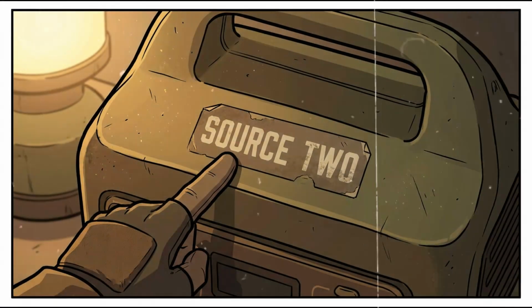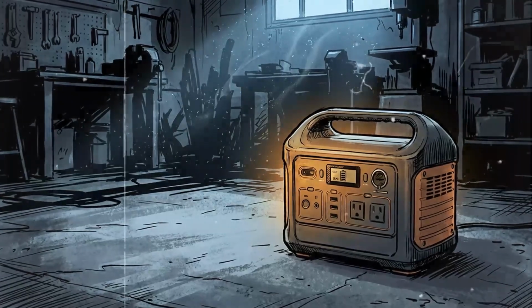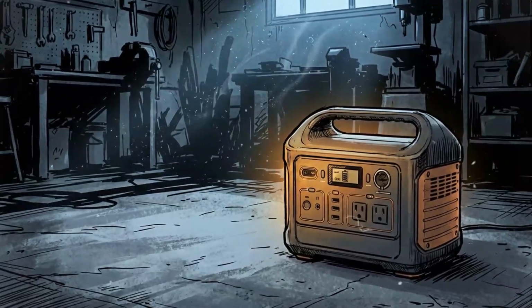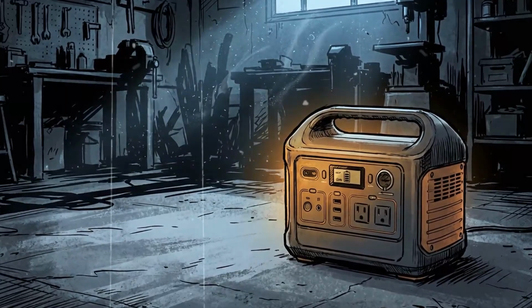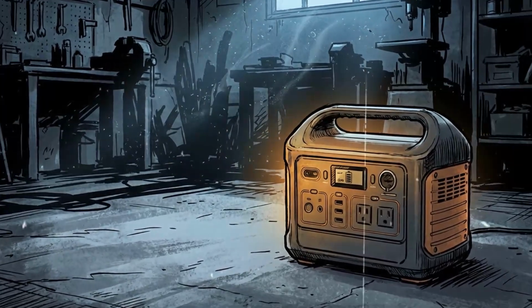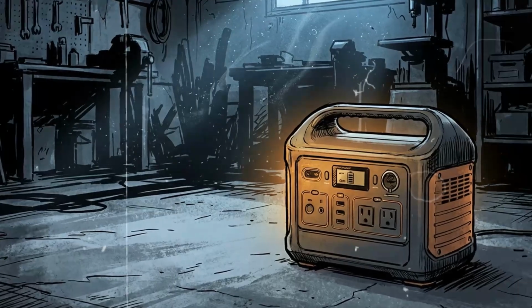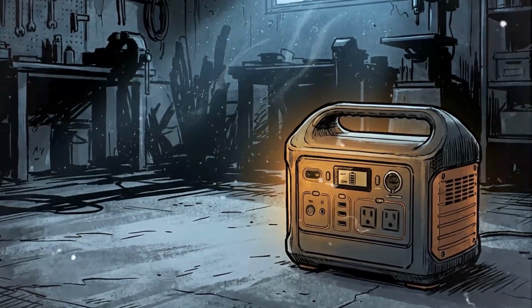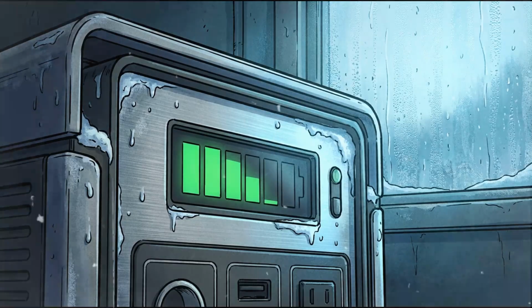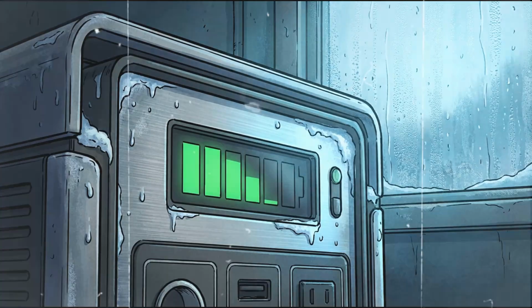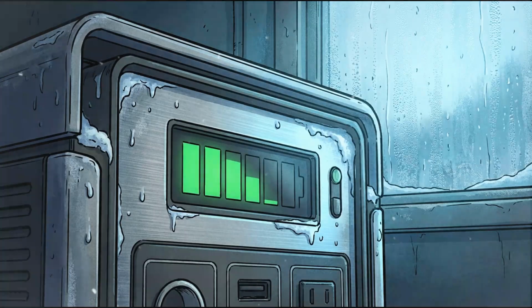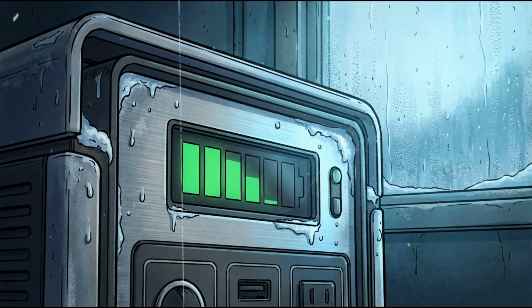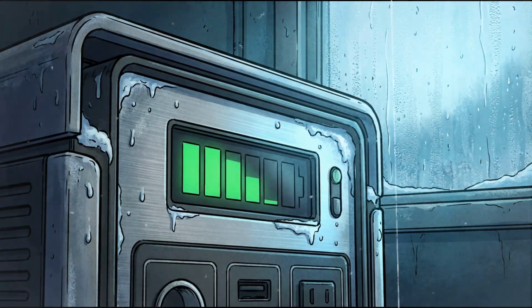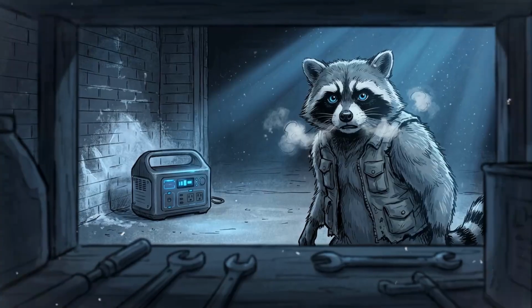Source 2, portable power station. I tested a 1 kilowatt-hour unit, rated capacity 1000 watt-hours. Usable capacity at 20 degrees Celsius ambient temperature, 840 watt-hours. Battery chemistry loses capacity in cold. The lithium cells in this unit are rated for their full capacity at room temperature. Drop to near freezing and you lose 15 to 20%.